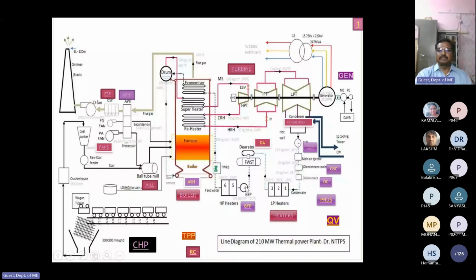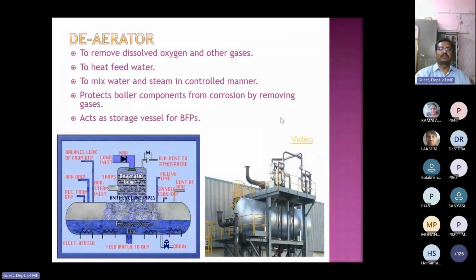Next, I will show the deaerator. The purpose of the deaerator is to remove the dissolved oxygen and other gases and to heat the feed water. It mixes the water and steam in a controlled manner. It protects boiler components from corrosion by removing gases. If gas exists in the water, corrosion will occur inside the boiler.